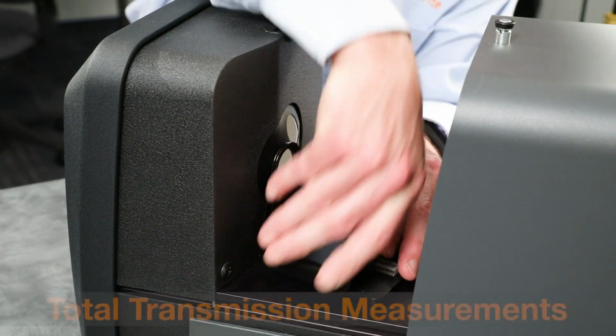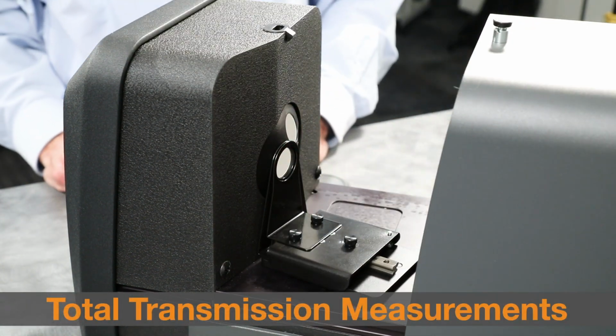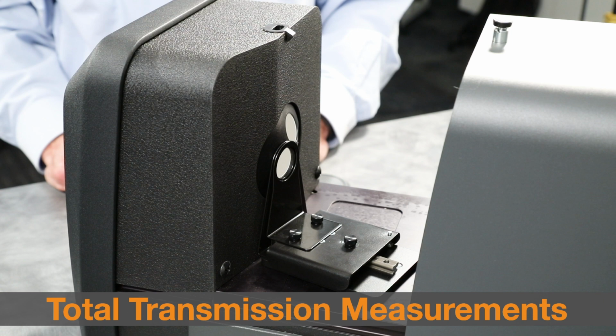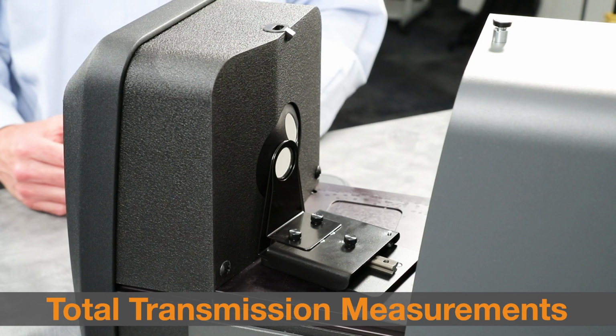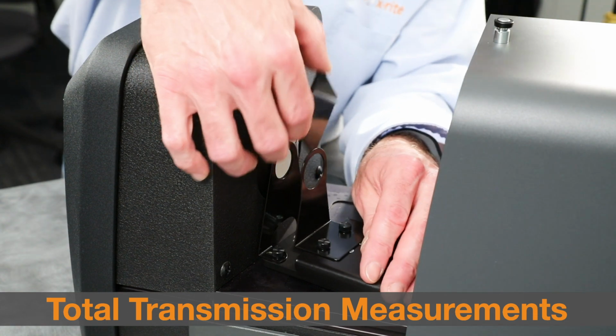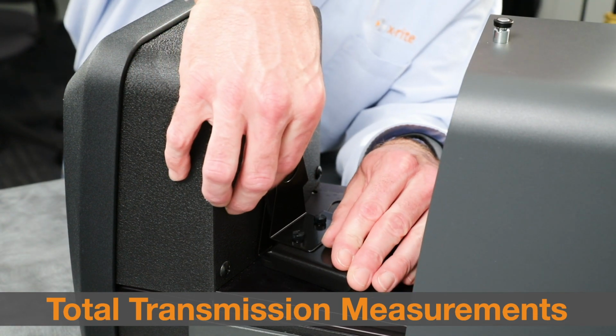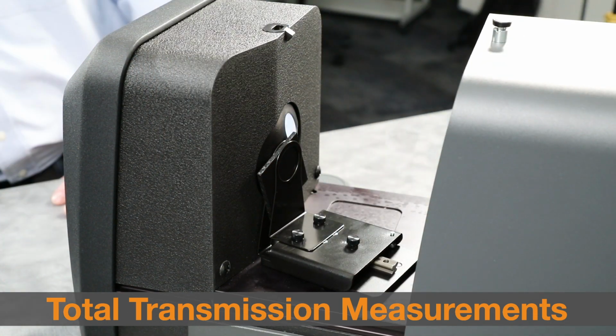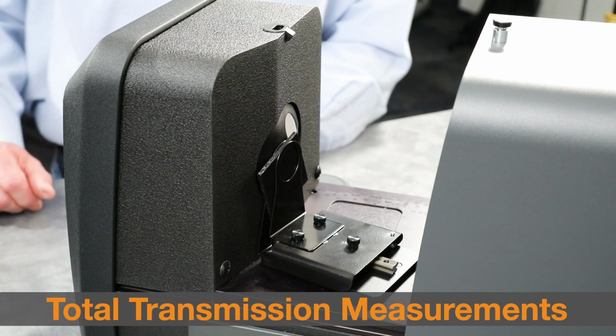For total transmission measurements, place the transmission holder inside the transmission compartment so it faces towards the sphere. It should sit in two notches to help ensure the correct placement. Center the black plastic blocking panel on the transmission sample holder, and take the reading through your software.